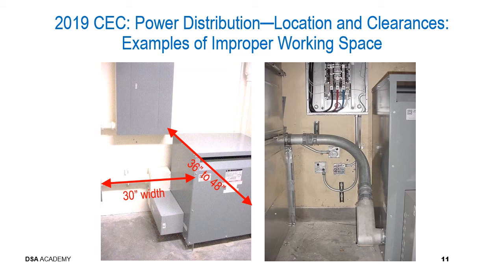If you look at the image on the right hand side, we have something very similar, where we have a panel mounted to the wall, and as you can see, there's a giant piece of conduit coming from the left in front of the panel and below the panel, and then swoops down out further in front of the panel, hits an LB, and then shoots into what appears to be, again, maybe a transformer. Obviously, we've got the same situation happening here that makes this improper, that this conduit and the LB actually extends out further than the permitted 6 inches in front of the face of the panel itself. So be aware of these types of non-compliant conditions.